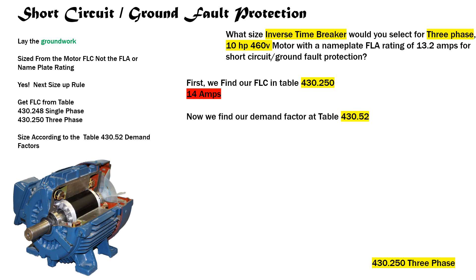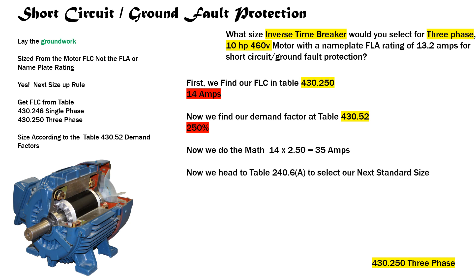Now we'll find our demand factor in table 430.52. We start on the left-hand side with our type of motor, then come across to our type of overcurrent protection — inverse time breaker — and we find that it's a demand factor of 250 percent. Now we do the math: 14 multiplied by 2.50 gives us 35 amps.